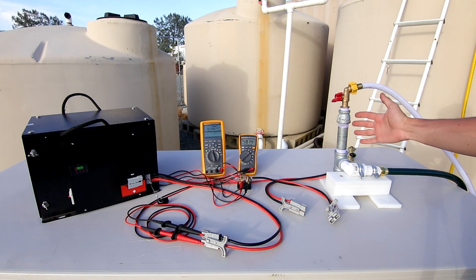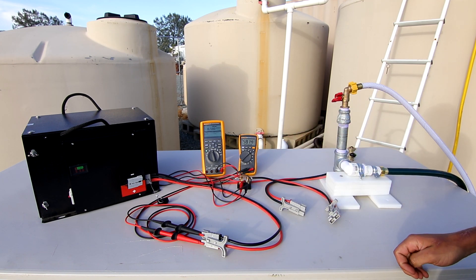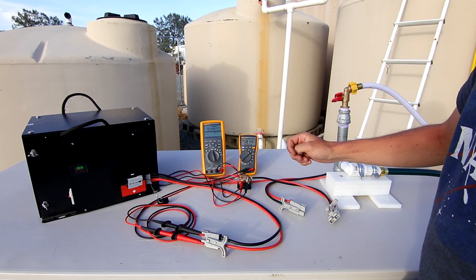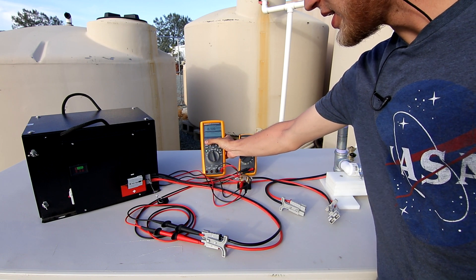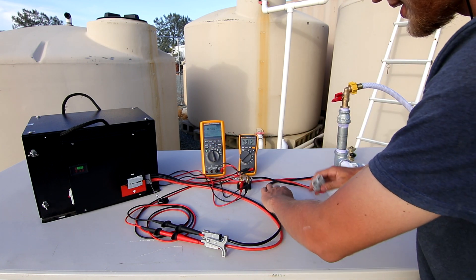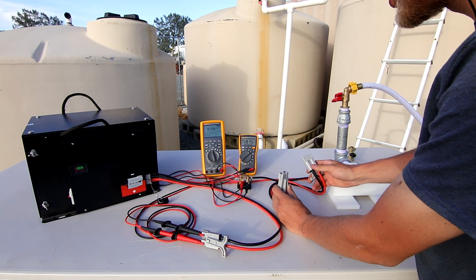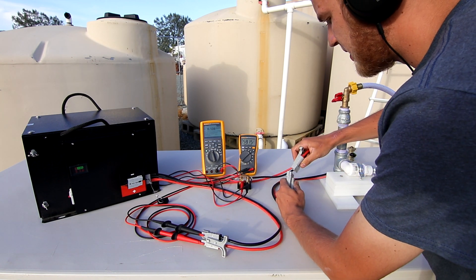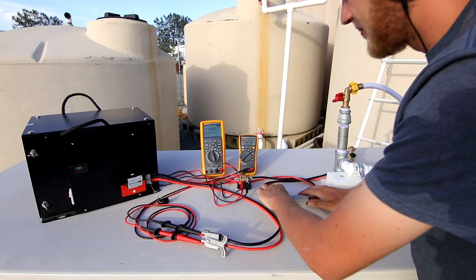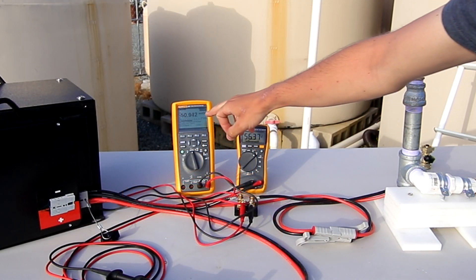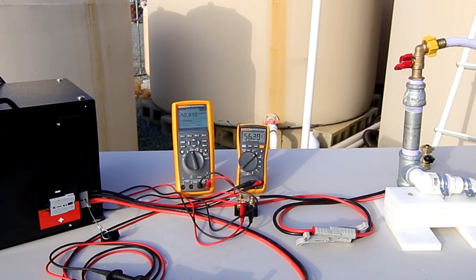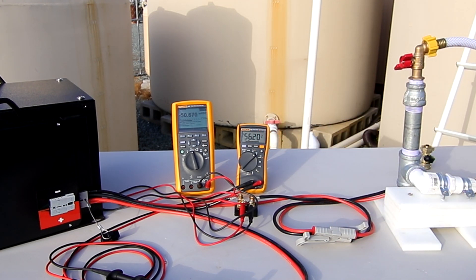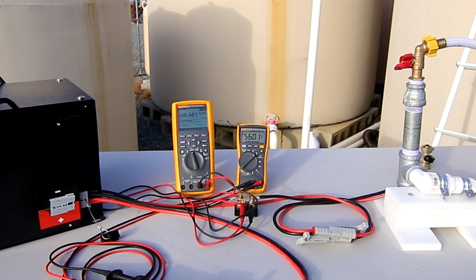So now I have water running through this dummy load. I'm reading about 58.1 volts, my meter is ready to record, so I'm going to hit the record button and start it. Now I can connect my test load and we'll begin our capacity test. We have 50.8 amps coming out of this battery and our voltage has dropped slightly to 56.2 volts. I'm going to run this and log when the low voltage alarm kicks on and then finally when the battery cutout takes place.